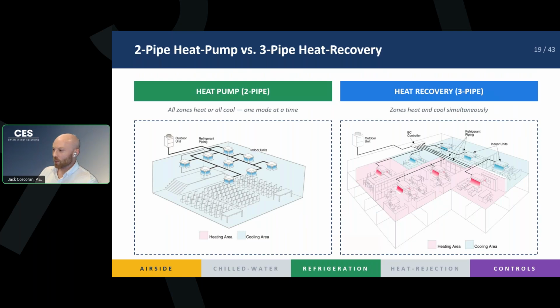The reason for the 3rd pipe is it is an intermediate vapor, right, that's going to run to our coils. It basically transfers heat between our zones instead of transferring that heat all the way back to the outdoor unit to then send it to the indoor unit, right? So you can imagine in the zones that are in cooling, right, you're pulling heat into our refrigerant, right? But if there's another zone across the building that needs heat, you can pull the heat out of our cooling zones and send it to our heating zones without running it through the compressor. That's a very, very powerful energy savings. And it's actually the best part about our VRF systems.